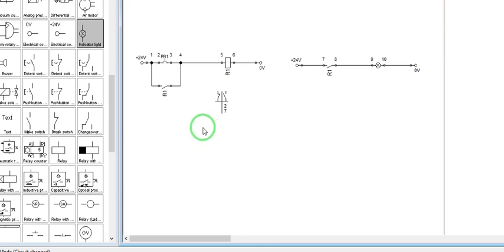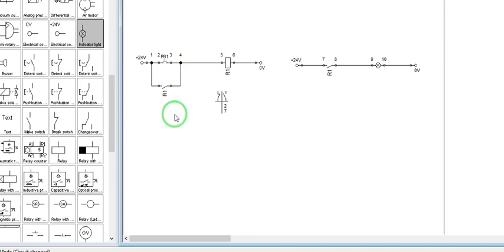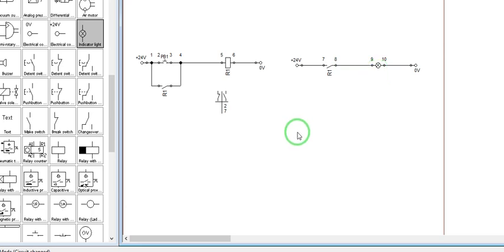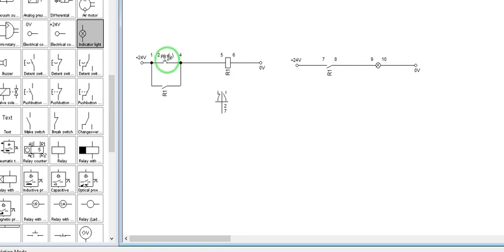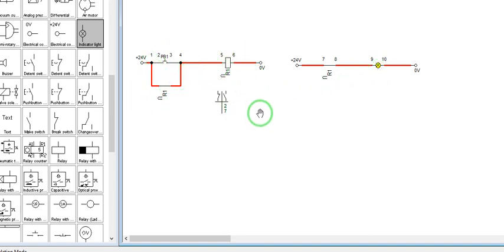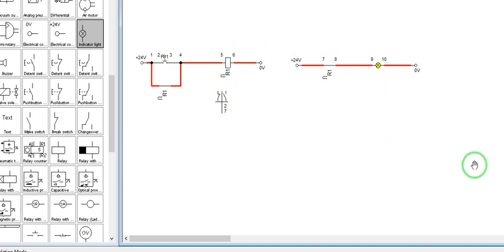I have already prepared the diagram for the latching circuit. As you can see, we have Push Button 1, Relay R1, and this is our control circuit. We have the auxiliary contact R1, and for our load circuit we have another auxiliary contact R1 and our lamp. If you run this simulation and press and release Push Button 1, R1 will latch, thereby energizing our lamp. However, there is no unlatching component in this circuit, so the only way to unlatch is to power off the circuit — in the simulation, we stop the simulation to de-energize the relay.